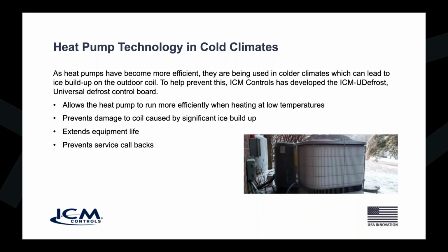What happens is that those cold temperatures lower the temperatures in the system, and then you develop frost, and eventually you create a thermal blanket around your heat pump's outdoor coil, which then means you get no thermal transfer. So the way a heat pump kind of works is that you're going to have latent heat in the atmosphere. And so even though you feel cold, oh my gosh, you feel like it's 32 degrees outside, it's freezing, but to a heat pump, there's a lot of latent heat there. And so it will absorb that latent heat, and then by the process of evaporation and condensing the refrigerant, we can push heat out the indoor coil.